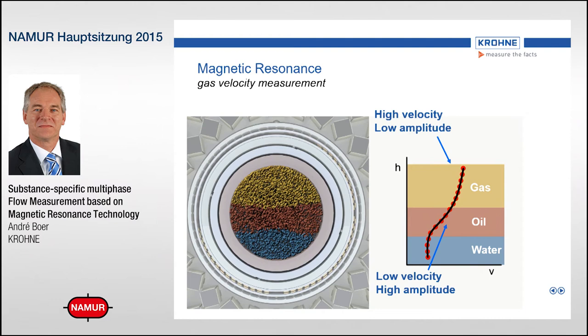At the top part of the pipe, you will typically see high velocity measurements and low amplitude, indicating gas is present there. In the midsection you will see higher amplitudes and lower velocities, and even lower in the pipe you'll see further lower velocities and similar amplitudes. By doing this imaging and slicing, we can find out how much gas was in the cross-section, at what velocity the gas was flowing, and we can do the same for oil and water.